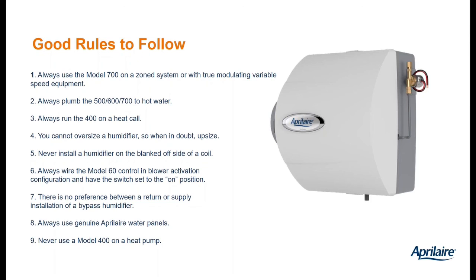The water panel is not going to start to slump. A lot of knockoff water panels will slump over time. That can cause two very different problems. One is if they slump at the top, you can get a gap that allows air to whoosh over the top of the water panel. That can blow water off of the water panel. That's entrainment. You can get water damage, corrosion, mold growth, all kinds of stuff.